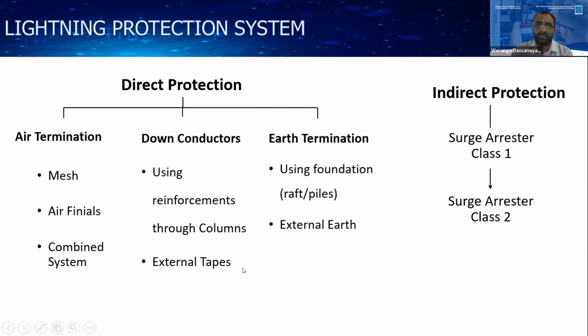consisting of these three systems. First one is air termination, second one is the down conductor system, and third one is the earth termination system. Air termination means, I think you all have seen a rod installed at the top of the roof level in most buildings. That means the lightning is absorbed by that air termination system. That air termination system can be done with a mesh. That means you can use a mesh on the rooftop or roof slab to absorb the lightning, or the air finial. Or you can use these two as a combined system.